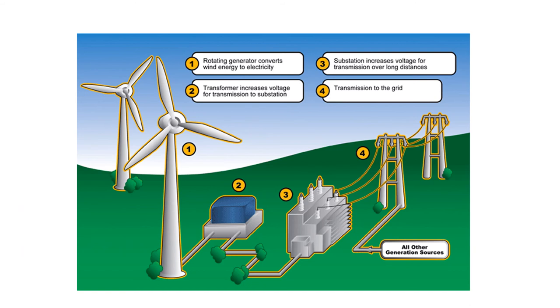The wind turbine is connected to the grid via an intermediate direct current circuit. The alternating current generated by the generator is first converted into direct current and then converted back into alternating current with the correct frequency and voltage. This enables variable speed operation of the wind turbine and minimizes mechanical stresses. The rotating generator converts wind energy to electricity, and the transformer increases voltage for transmission to the substation. The substation increases voltage further for transmission over long distances and to the grid.